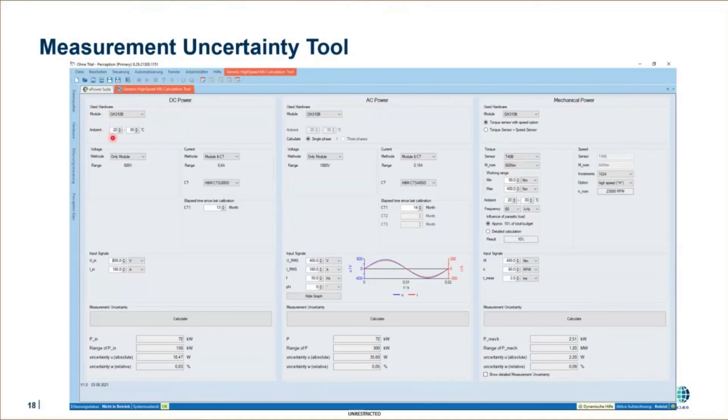Max temperature, the time which is elapsed since last calibration, all those side effects. And then you can calculate the measurement uncertainty. And what you get as a result is you get the specified power, which you measure, the power range and also the measurement uncertainty as absolute and also as relative information. And of course, this is the first step to do that offline for steady state operating points. But you can imagine the long term goal is that we specify that with the measured value.